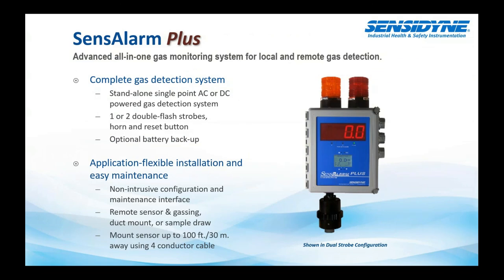Our SensAlarm Plus is a complete gas detection system, standalone, single point, AC or DC powered, double flash. You can have a low level alarm or a high level alarm, both in there, and it also has an audible horn built into it as well. These can be remote mounted up to 100 feet away, as we discussed, and are really good for placing at an entry to a room where you might have some exposure to low oxygen. You could have a worker walk into a low oxygen environment and drop dead right there and never know what hit them. This way they're not walking into those hazardous environments. It's being monitored. They have the security of knowing that this is a safe location before entering the building or space.